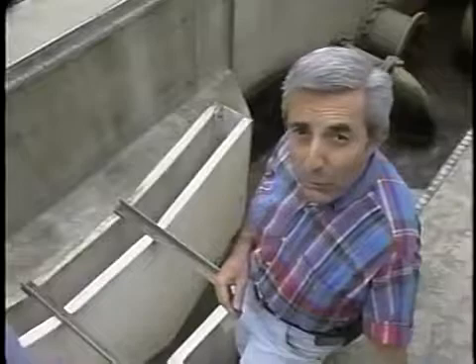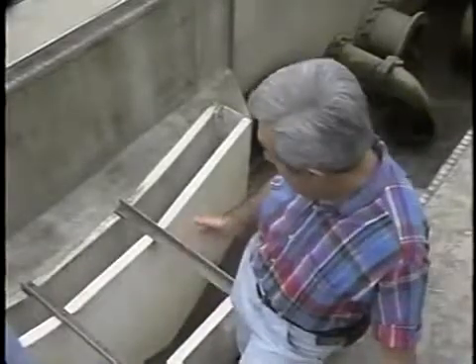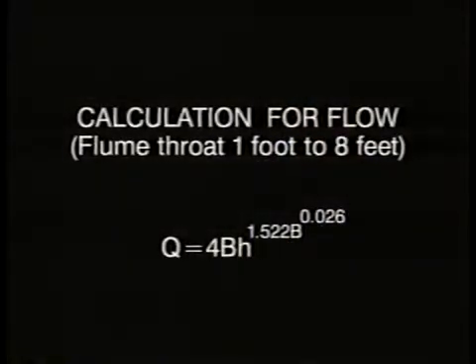The principle for flow measurement in a Parshall flume is that channel restriction here at the throat produces a calibrated change in the liquid level and flow velocity as the flow rate varies. There are several equations, depending upon the size of the flume, for measuring the flow in a flume. The basic formula relates the flow Q to the liquid head, where Q is the flow in cubic feet per second, B is the throat width in feet, and H is the liquid head in feet measured at a specific point in the convergence section.